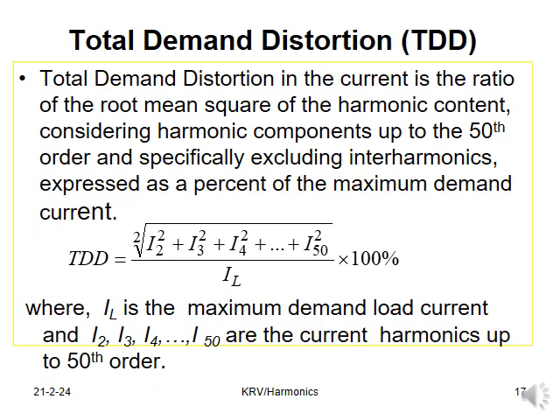Total demand distortion in the current is the ratio of the root mean square of the harmonic content considering harmonic components up to the 50th order and specifically excluding interharmonics, expressed as a percentage of maximum demand current. TDD is equal to square root of I2 square plus I3 square plus I4 square plus up to I50 square, divided by IL, multiplied by 100%, where IL is the maximum demand load current and I2, I3, I4 up to I50 are the current harmonics up to 50th order.